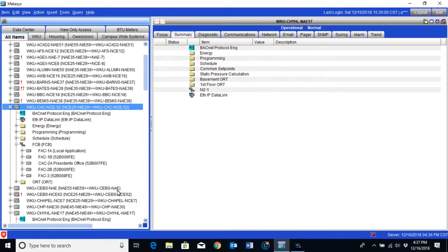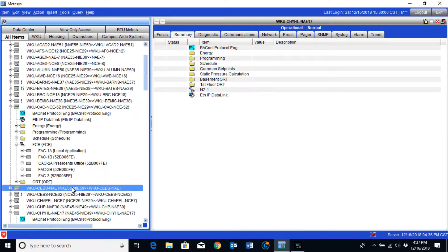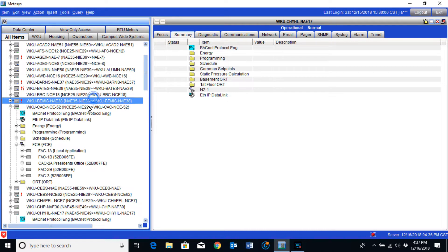When you get into a lot of buildings that have a lot of devices, you may be limited on the type of NCE that you can go with. That's where an NAE will generally come into play. You can get these larger NAEs that are able to handle a lot more points. But if you're doing a simple air handler control or you have a small facility, an NCE may help eliminate the need for a controller — such as an FEC — and still give you the ability to talk to the remaining devices within your building, such as VMAs or hot water system controllers.